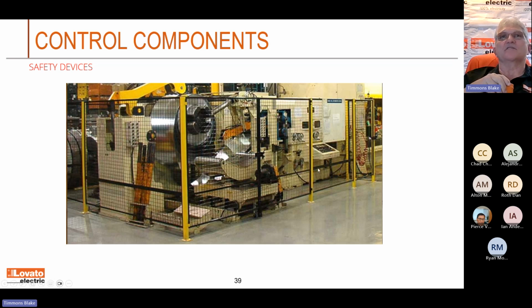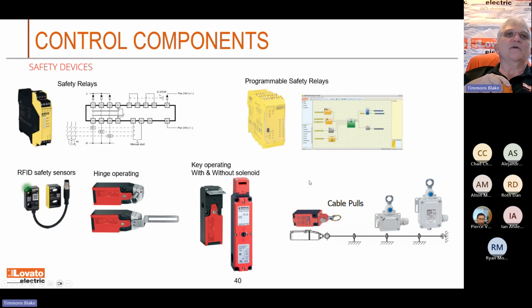Your safety devices, you can imagine all the different places you can put a safety device on these things. We have safety relays. And one of the things I look for when I'm crossing these safety relays and trying to help somebody get one is how many safety devices. Can you see that in the upper left corner? You've got K1, K2, K3. This has got 3 contactors in series for safety. And I've got a way to control that with our safety relay. Sometimes you'll see that in 2s or 1.